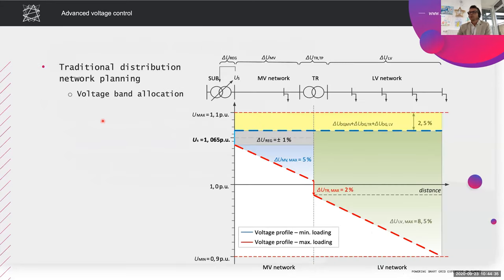And what do you do if you have a poorly observable system? If you don't have much data on what is actually going on in your system, if you don't have the measurements, of course, you have to make the distribution network robust enough that it can withstand all possible operating conditions. This means that no matter what the user does, the voltages will be okay.